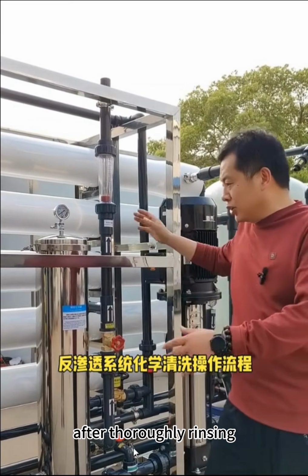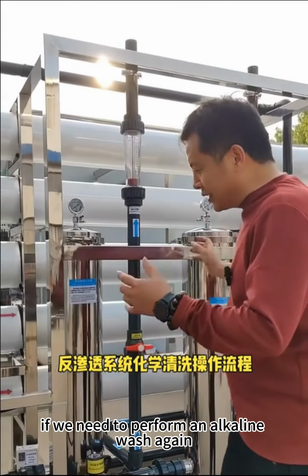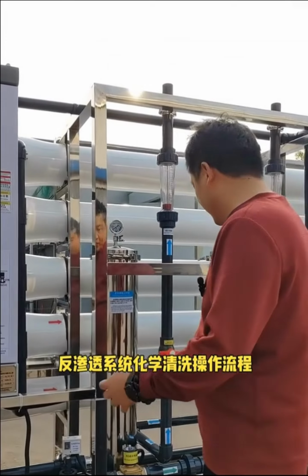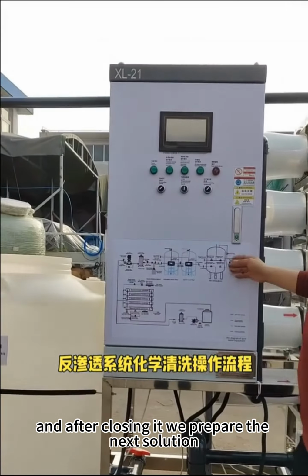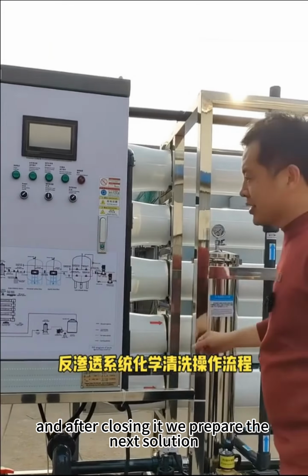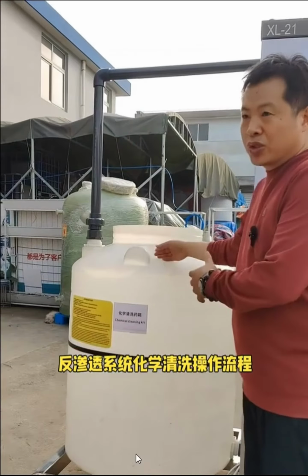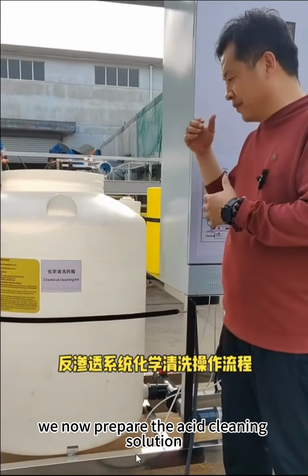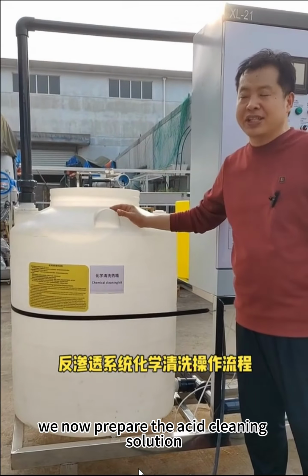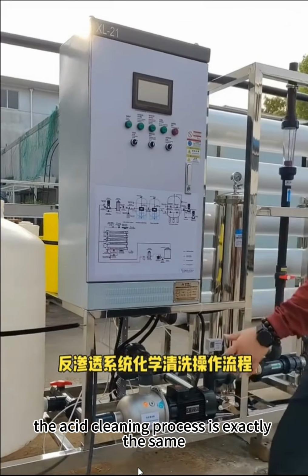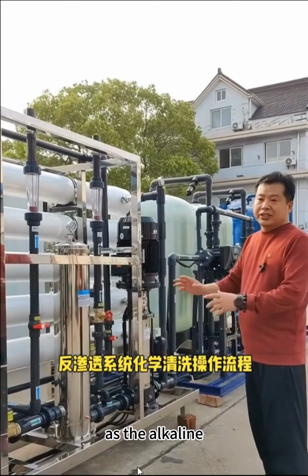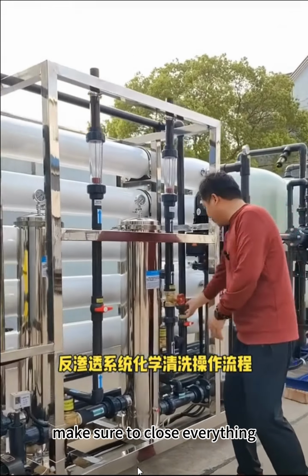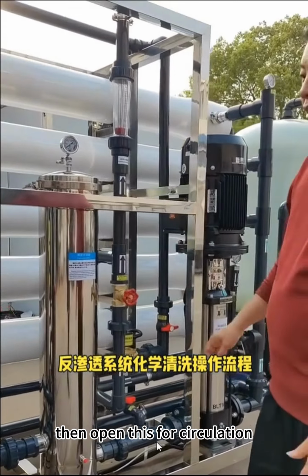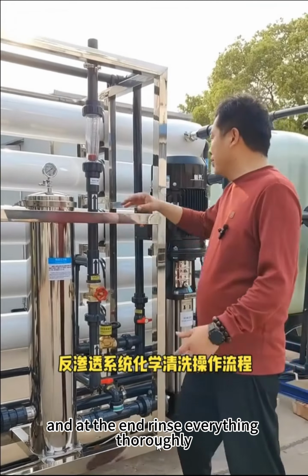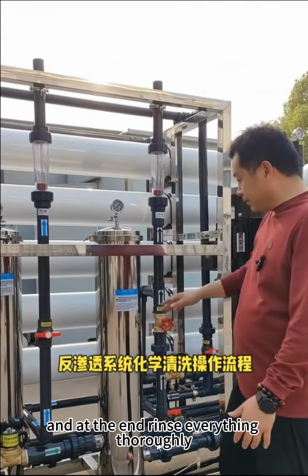After thoroughly rinsing, if we need to perform an alkaline wash again, then we close this, and after closing it, we prepare the next solution. If we just did an alkaline wash, we now prepare the acid cleaning solution. The acid cleaning process is exactly the same as the alkaline cleaning process. Make sure to close everything, then open this for circulation, and at the end, rinse everything thoroughly.